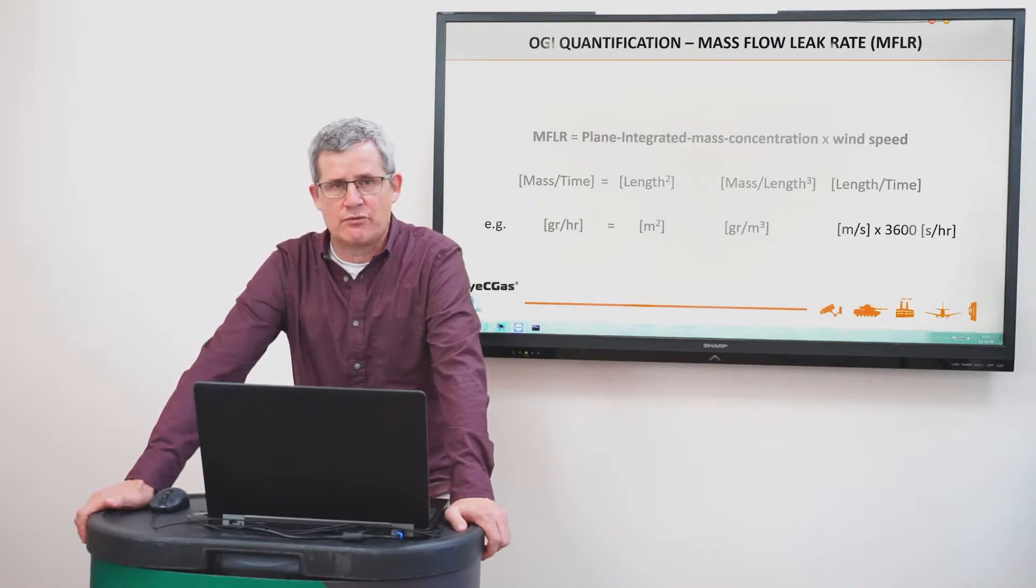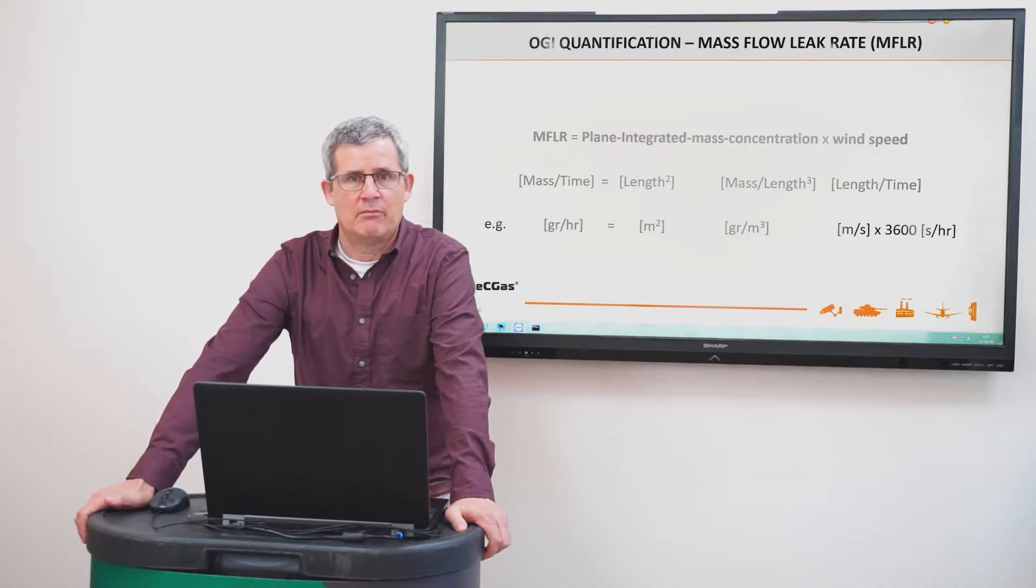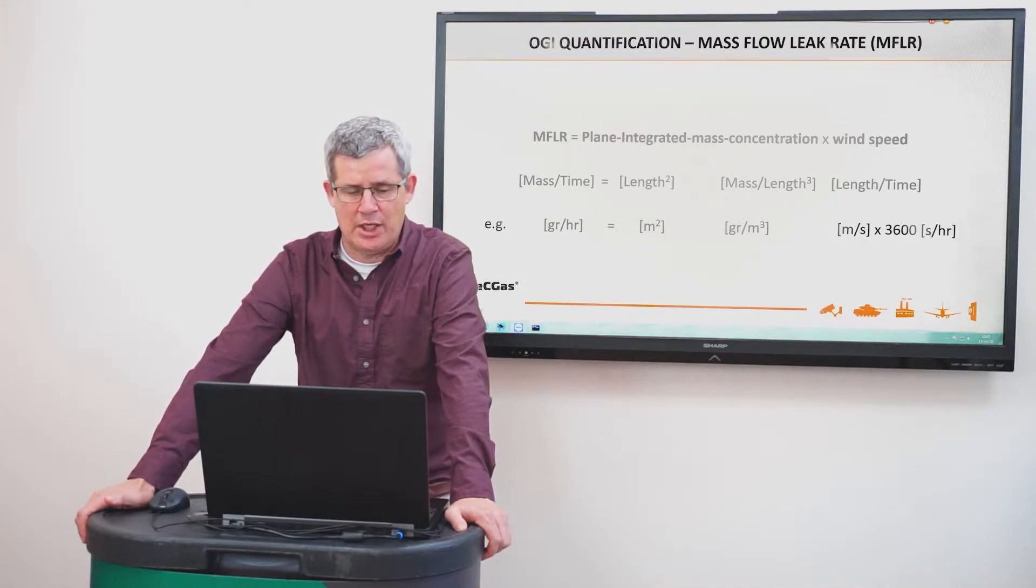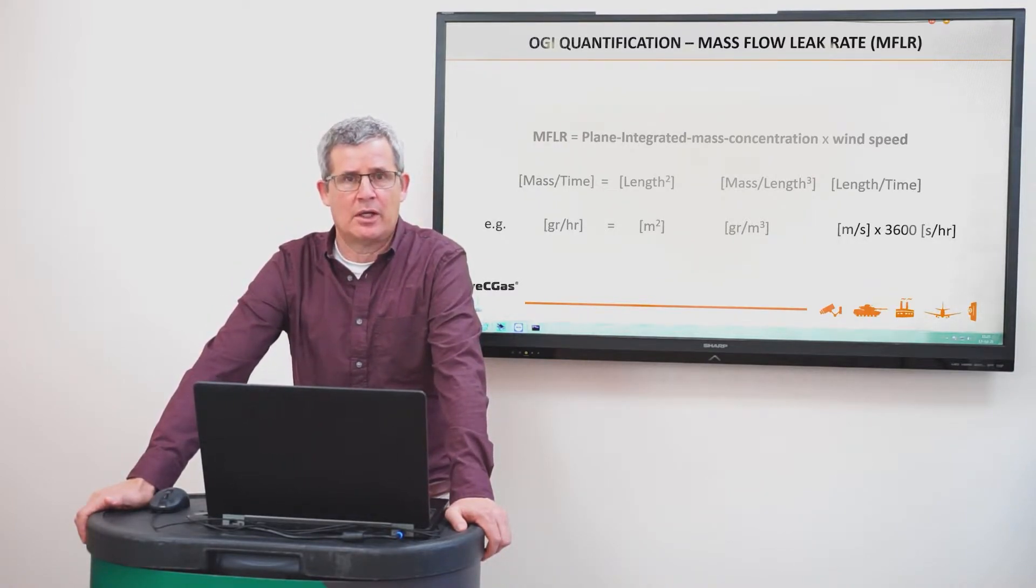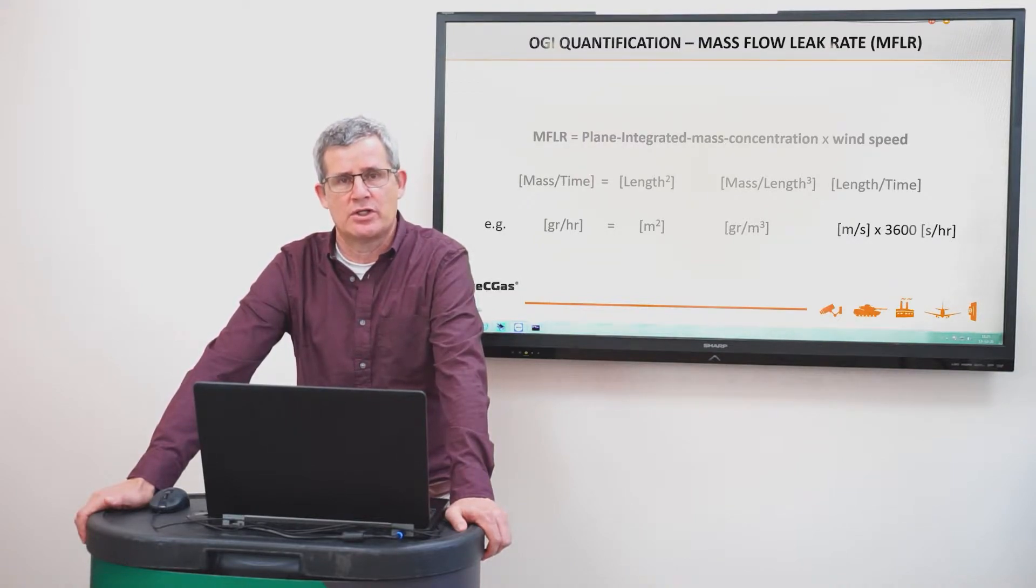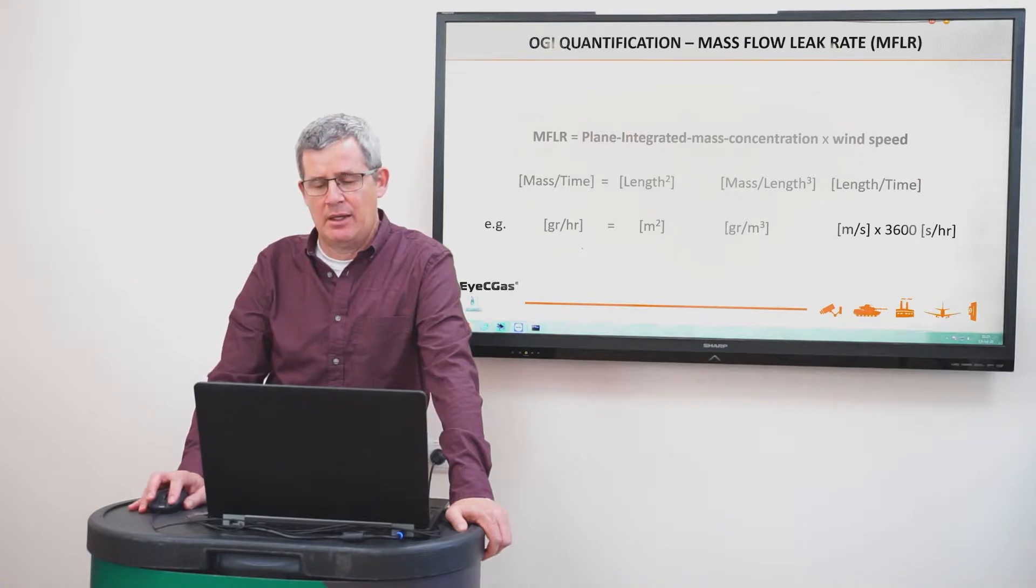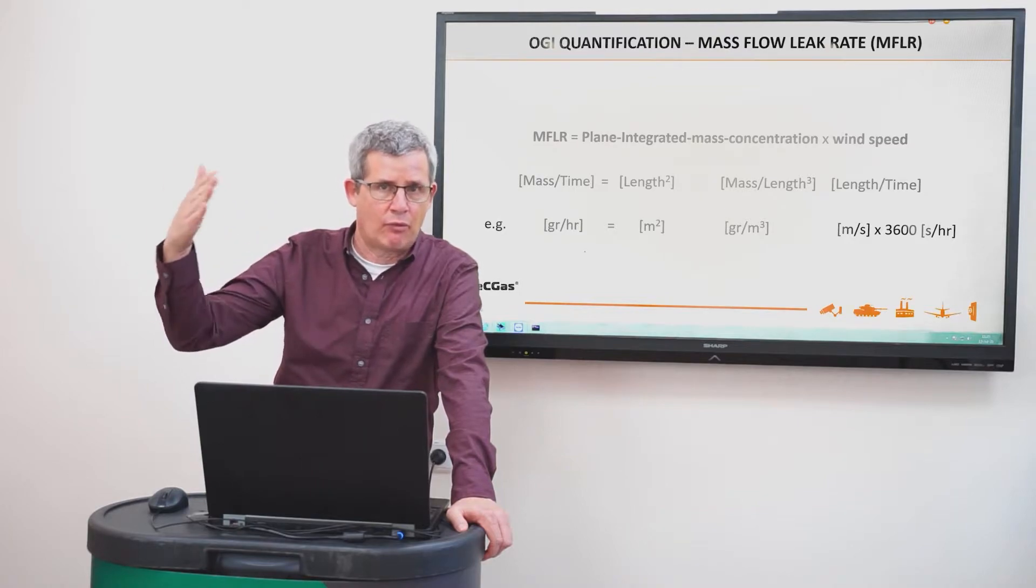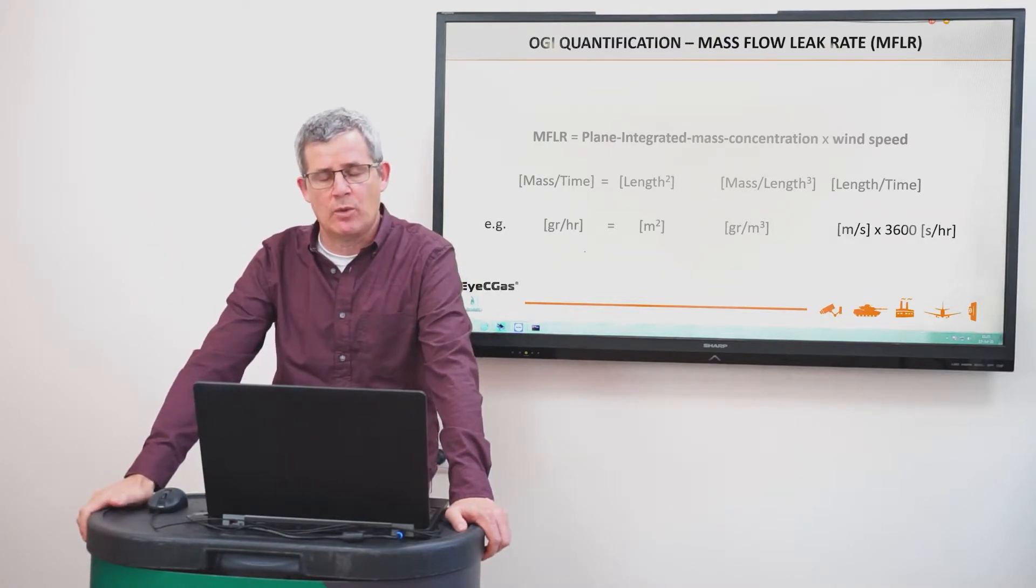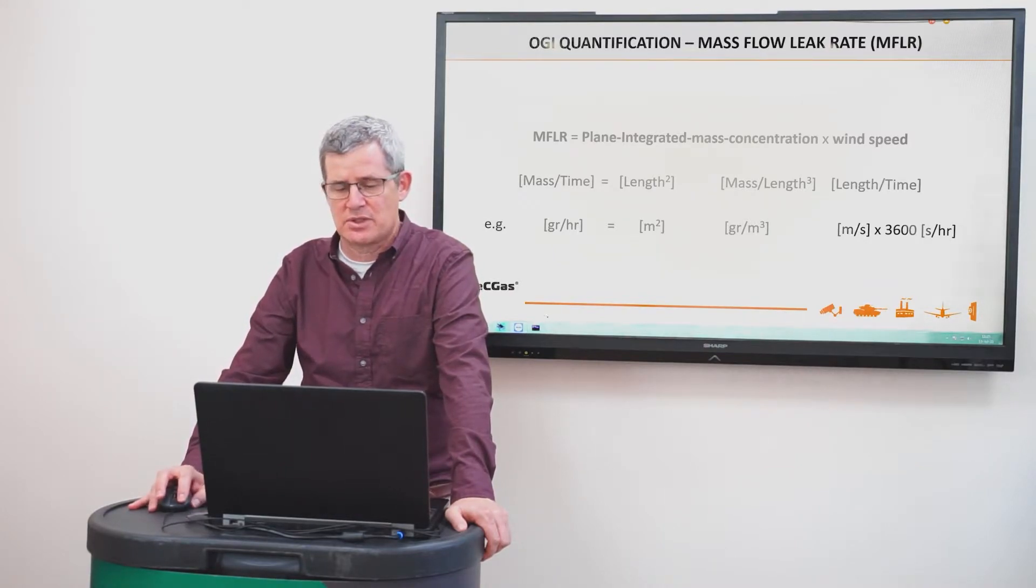The mass flow leak rate or the emission rate or fluxes are all the same for quantification with OGI. So basically when we talk about the leak rate we are talking about a mass that goes through a concentration, integrated concentration that goes through a plane, not through a plume, through a plane. And in order to know the rate that it goes through the plane we need to know what is the wind speed. So it's essentially the product of plane integrated mass concentration times the wind speed.